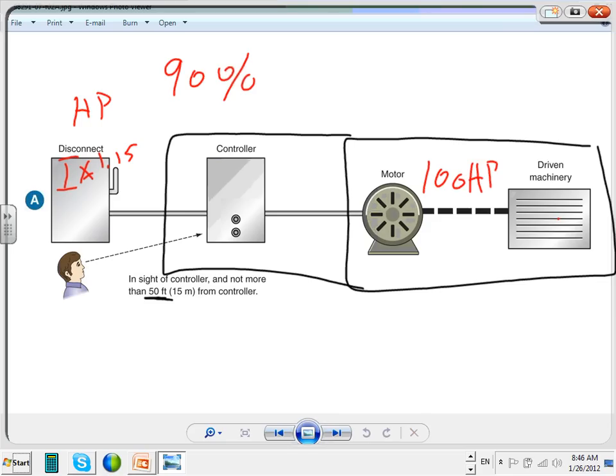Horsepower rating, if this happened to be 100 horsepower, then I need a disconnect that is able to interrupt a 100 horsepower motor. So disconnects that drive motors, guys, are rated in horsepower and amps. Anybody know why horsepower and amps? Because interrupting energy that's going to a rotating machine is more dangerous than interrupting energy that's going to a light or a heater. There's electromagnetic kickback. So this one has to be rated for horsepower, meaning it will be able to interrupt the power at that amount of power.